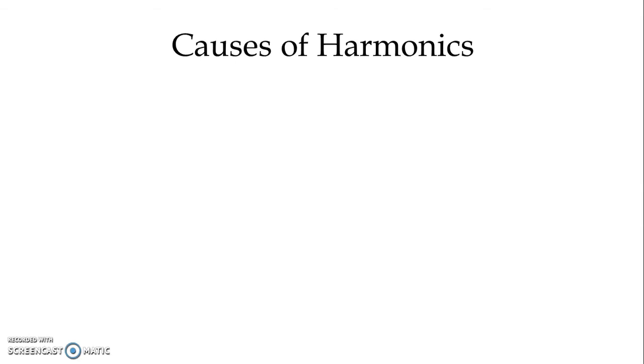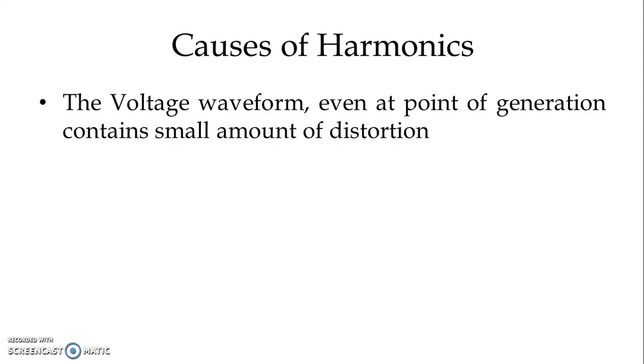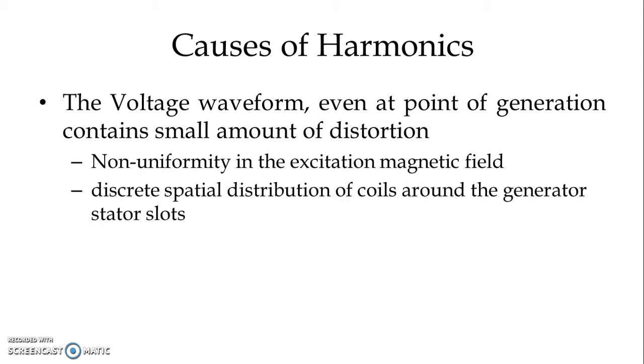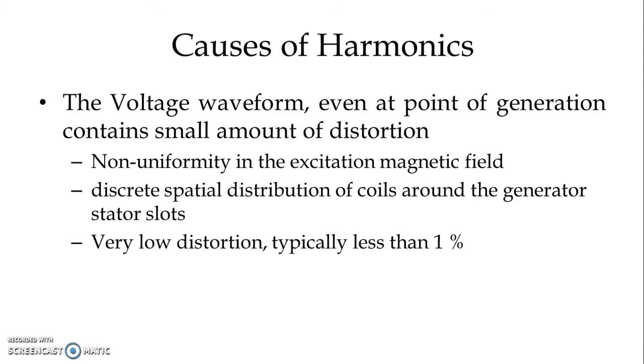We know that in case of harmonics, we have voltage harmonics as well as current harmonics. Starting with voltage harmonics, a pure sinusoidal voltage waveform is just a hypothetical quantity. Practically, a pure sinusoidal voltage waveform might not be possible. The voltage waveform even at the point of generation contains a small amount of distortion, and that may be because of non-uniformity in the excitation magnetic field as well as discrete spatial distribution of coils around the generator stator slots.